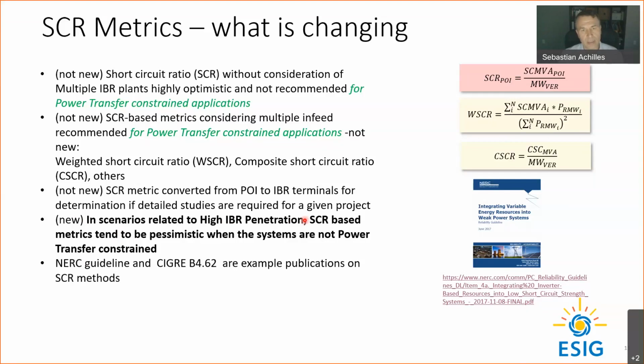In those cases, the short circuit ratio calculations typically recommended, including the multi-in-feed approach, tend to be quite pessimistic. We're finding many cases where the estimated short circuit ratios are below 1, which would normally be very concerning. But actually the plants work, the detailed studies are performed, the plants are commissioned, and there are no issues.